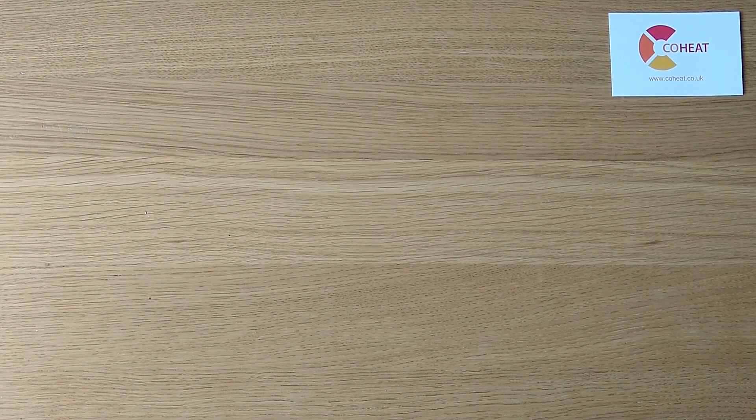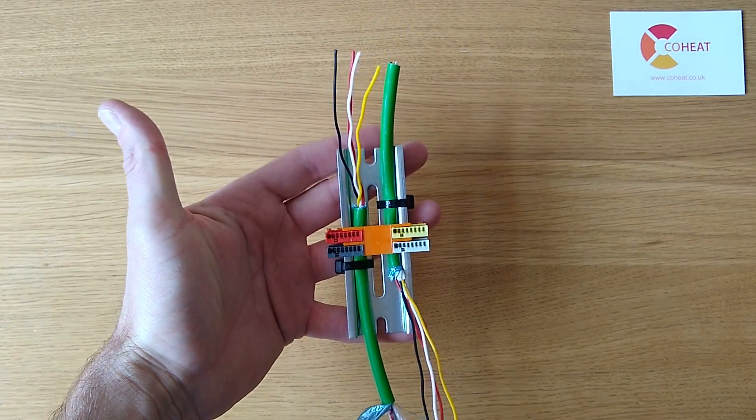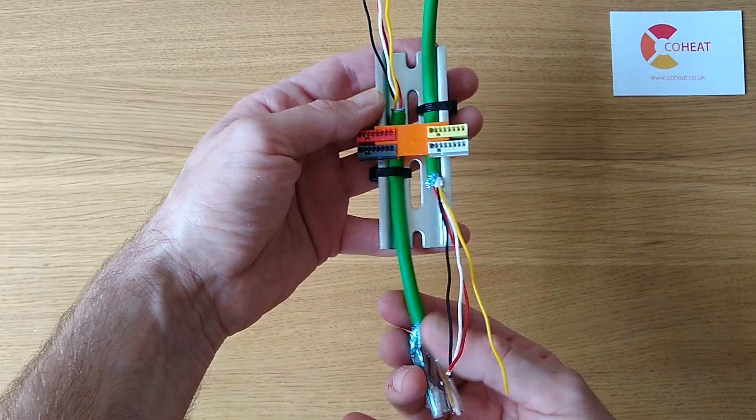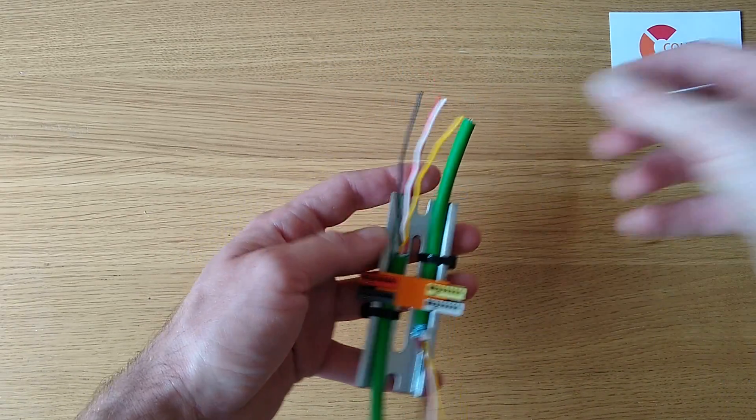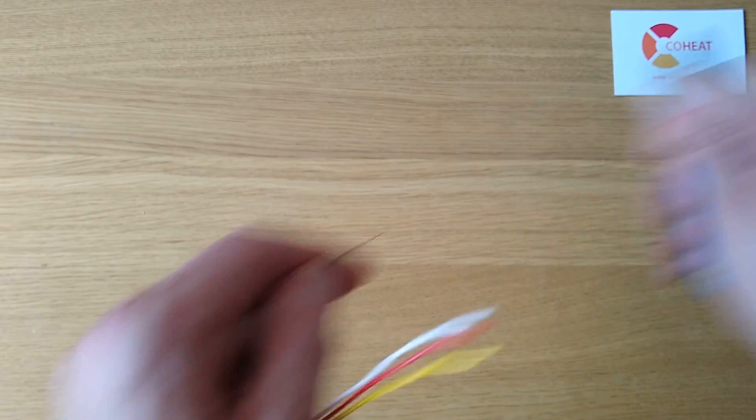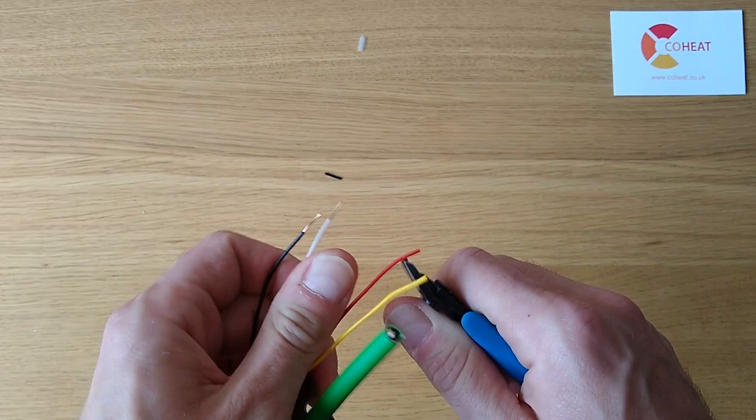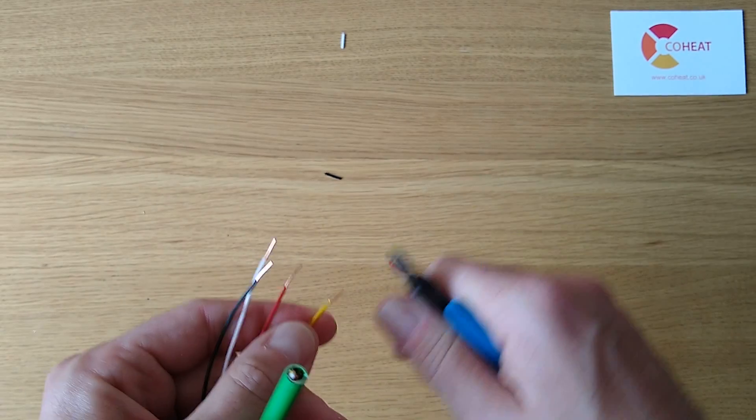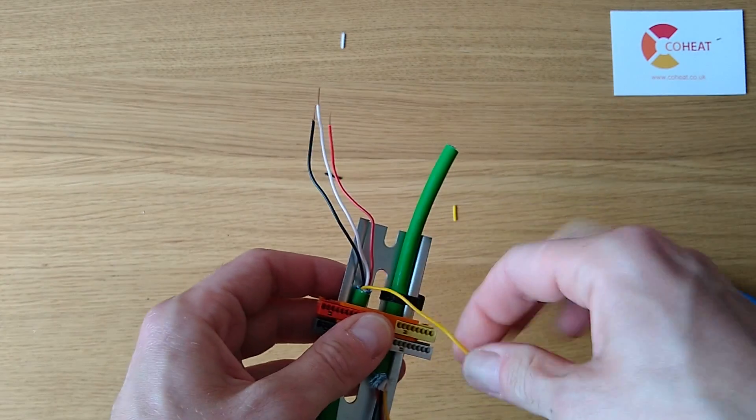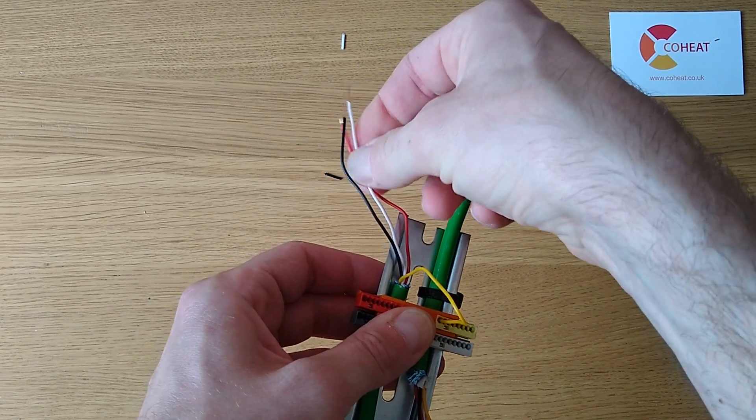When you're back at the junction box, say for example you have several HIUs coming back to a riser, I prefer this KNX style cable, with the KNX connectors inside some waterproof box. This could be our spine cable coming up, going forward. We take a pair of strippers, strip it, trim off any excess.